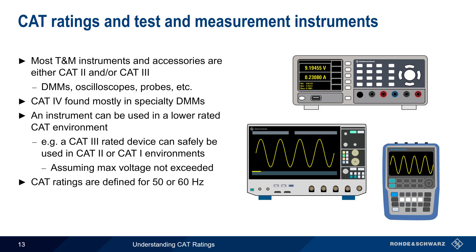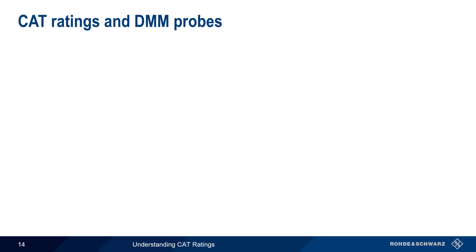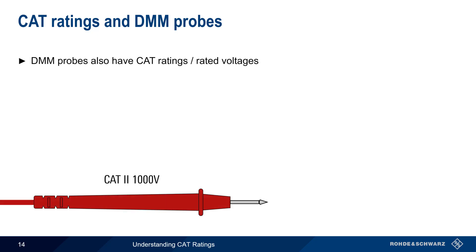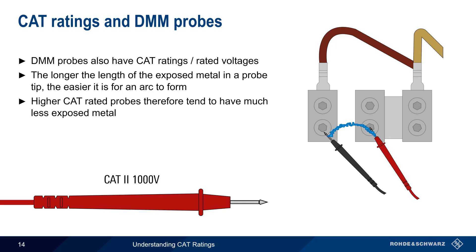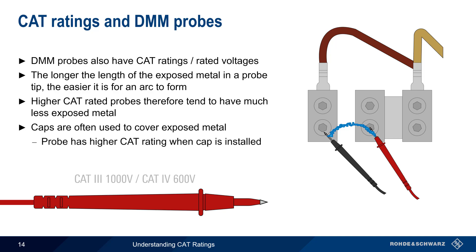One final thing to note is that CAT ratings apply only for 50 or 60 Hz AC. A different rating may apply when instruments are used to measure higher frequency voltages. The probes used with DMMs also have CAT ratings and rated voltages. Generally speaking, the longer the length of exposed metal in a probe tip, the easier it is for an arc to form. Therefore, probes rated for use in higher CAT environments tend to have much less exposed metal. Non-conductive caps are one method used to cover exposed metal, and some DMM probes will have a higher CAT rating when this cap is properly installed.